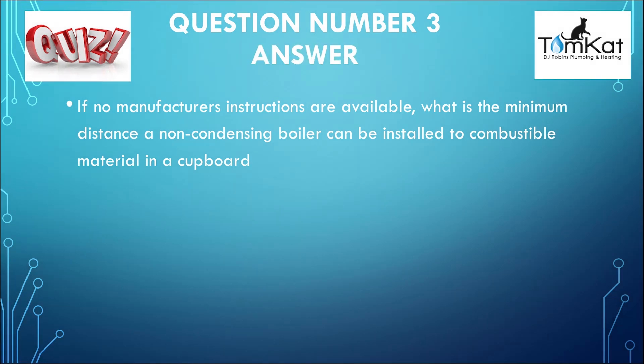So are you proving me wrong so far? Have you got two out of two? Are you going to make it a hat-trick? Let's look at the answer for question three: if no manufacturer's instructions are available, what is the minimum distance a non-condensing boiler can be installed to combustible material in a cupboard? The answer is C — 75 millimetres. That's the answer to question number three.